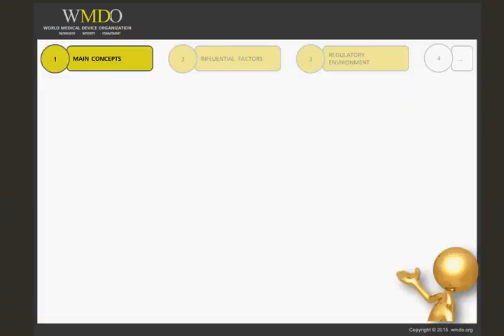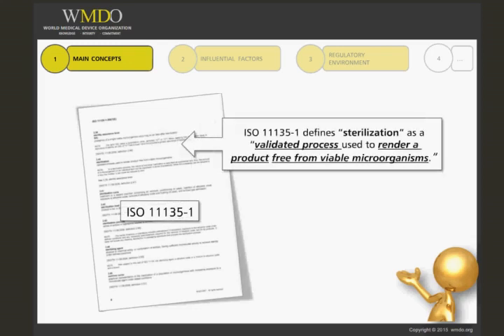Let's start by reviewing the main concepts of sterilization. ISO 11135-1 defines sterilization as a validated process used to render a product free from viable microorganisms. The definition contains two main ideas: first, sterilization is a validated process, and secondly, the sterilization renders a product free of viable microorganisms.